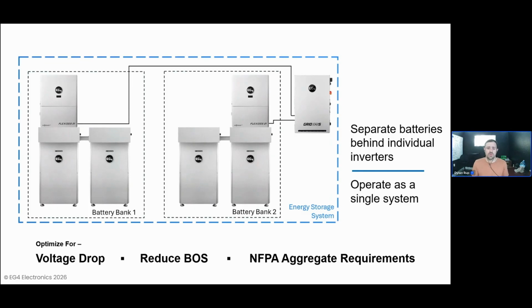Now, again, where that can become really important is situations where we're deploying large amounts of batteries and we want to minimize voltage drop. That's especially important in a 48-volt architecture, which the FlexBOSS line is. We don't want to have significant conductor runs where even a 1 or 2 volt drop from a percentage standpoint can be pretty significant as far as total power availability for the system. This reduces the balance of system required on site, where traditionally this might require significantly more conduit to get places or external combiner panels. That now has all been eliminated with this deployment.